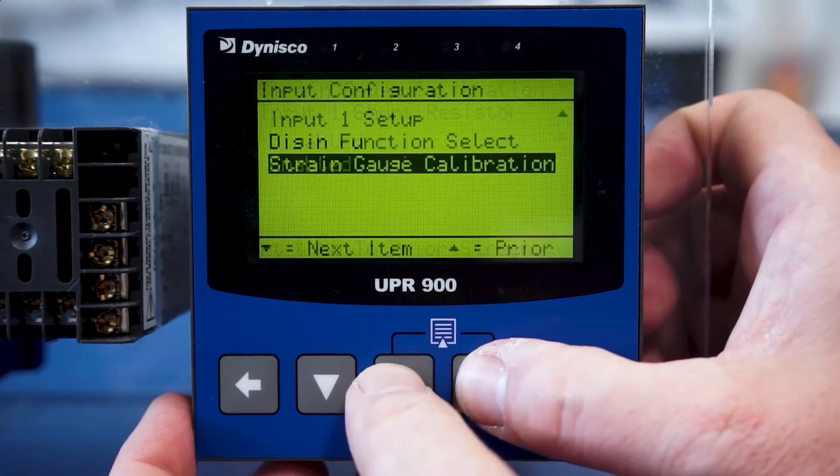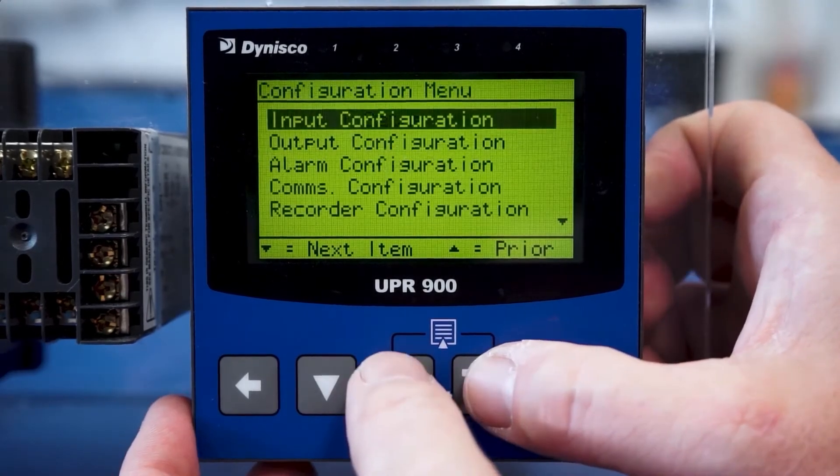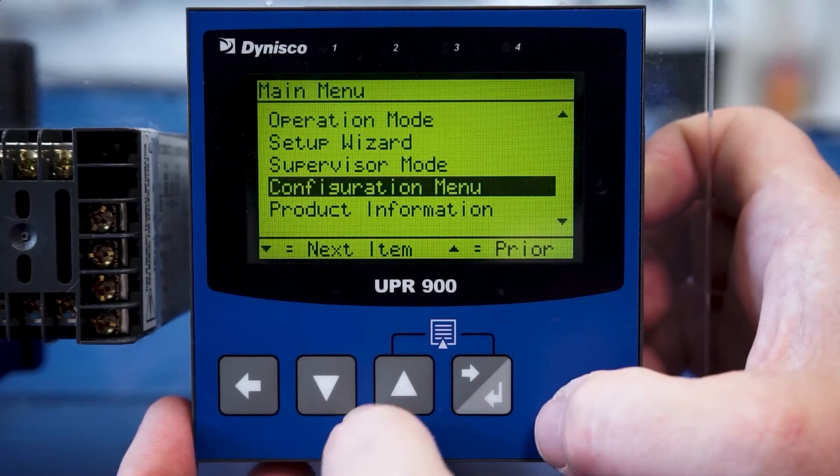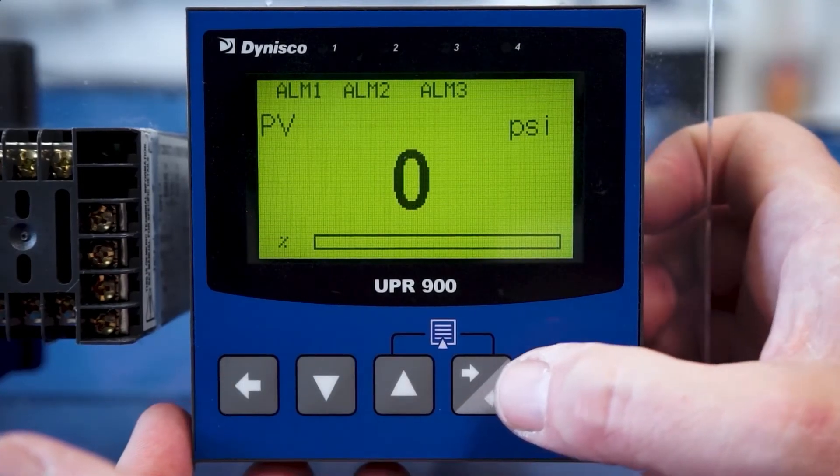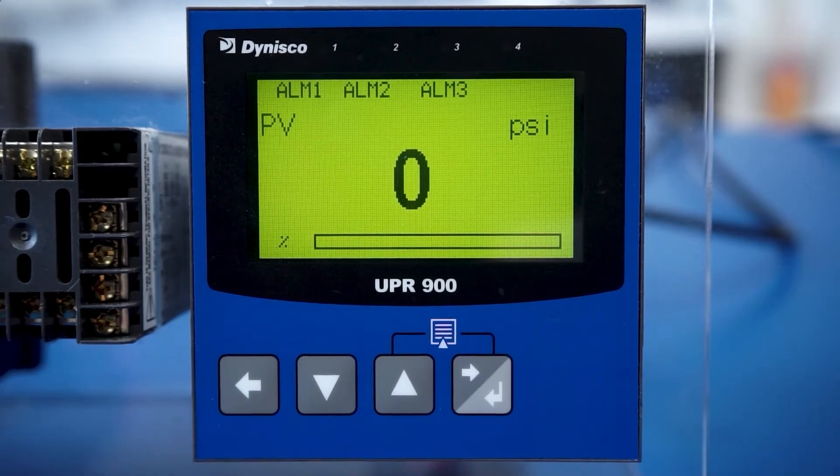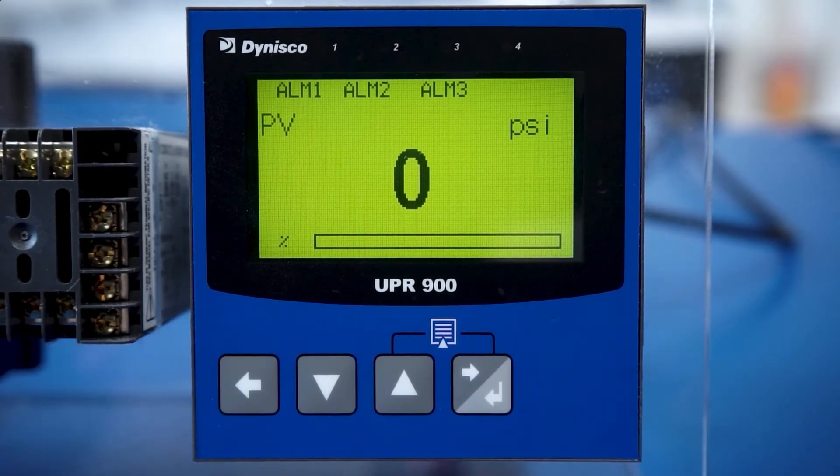With the sensor and instrument calibrated, the technician can then exit the configuration menu and select operation mode. Dynisco recommends this step be repeated any time the sensor exhibits pressure readings that appear abnormal or if the sensor has been swapped out.